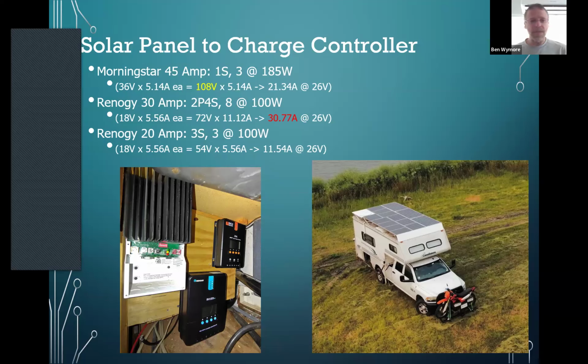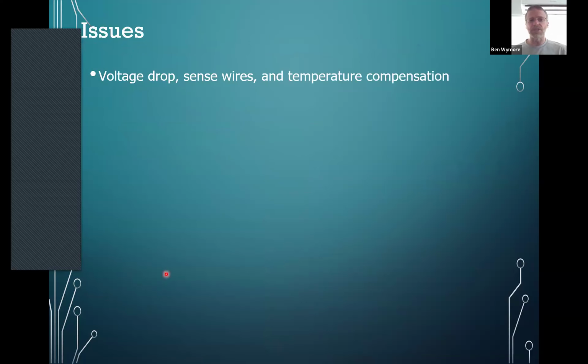This is a known problem, solved using what's called a sense wire. It's a separate set of wires attached to the battery, and the solar controller has a separate set of terminals for them. Because the current going through those wires is very small, just enough to detect voltage, there's negligible voltage drop, so the solar controller gets an accurate picture of what the battery is really at.